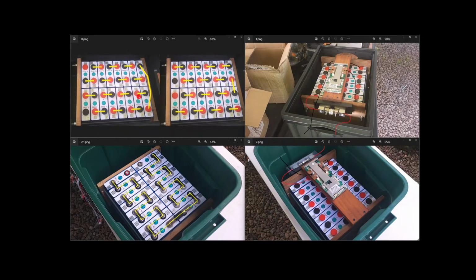One thing to consider is that the bus bars that come with these packs will not bridge this gap, so this connection over here isn't possible with a standard bus bar. Either way, you're going to have to build or make some kind of jumper or bus bar between these terminals. You could do that with battery cable and battery lugs, or if you've got flat bar stock of copper or aluminum, you could create your own bus bars.